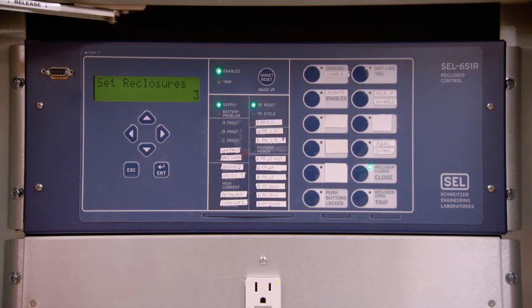There is what is classified as a 2-second dead time. What that means is when that fault occurs and the unit trips open, there will be a 2-second dead time before it will reclose to try that operation again. If the fault is still there, it will reclose into that fault and it will then trip out again. There will be a 2-second dead time, and it will continue this process until the number of recloses that it is set for is reached.